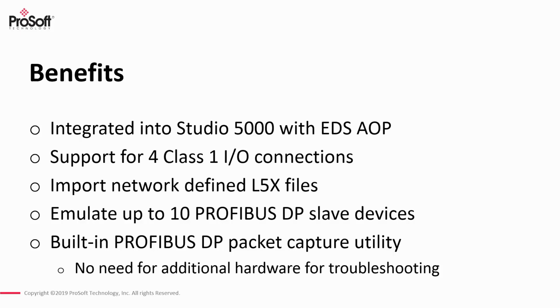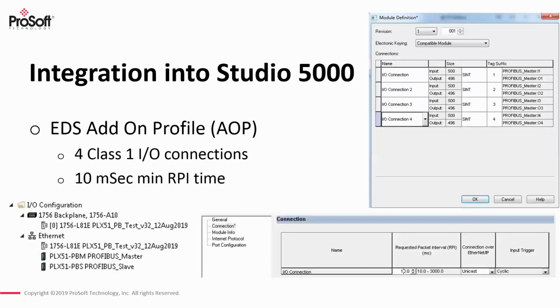And then one of the really nice features with this module is it's got a built-in PROFIBUS DP packet capture utility. So for anyone that's ever set up a Profibus network and had to start troubleshooting it because you had issues with getting communication between various devices, a lot of times that required putting a tap on the line and an additional piece of hardware to be able to take a look at the Profibus DP packets. This module has it built in, and so there's no need for additional hardware to do some advanced troubleshooting on the unit.